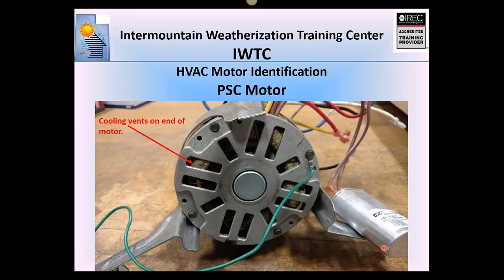Capacitors can be oval-shaped or round, and there will always be two wires on a PSC motor going to a remote capacitor. So if it has a remote capacitor, multiple speed leads going to individual pins, and cooling vents, you can guarantee it's a PSC motor.